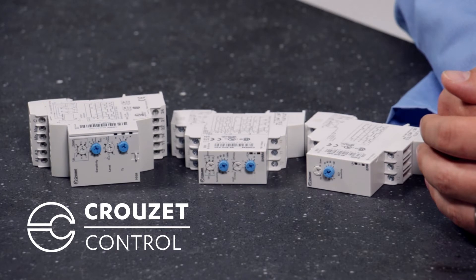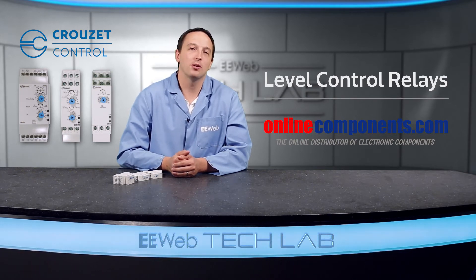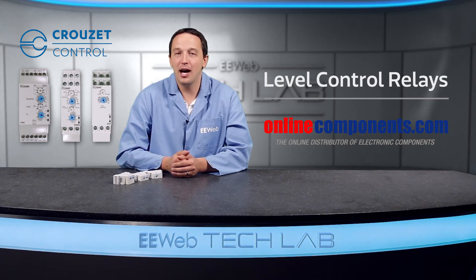Crouzet level control relays work by taking input from two level sensors, such as float switches, submersible probes, or capacitive sensors, and use the feedback from those sensors to determine if the pump needs to turn on. The pump can be used for emptying or filling, and certain models include a time delay function. This time delay prevents the relay from toggling on and off due to waves or ripples in the liquid tripping the sensors.